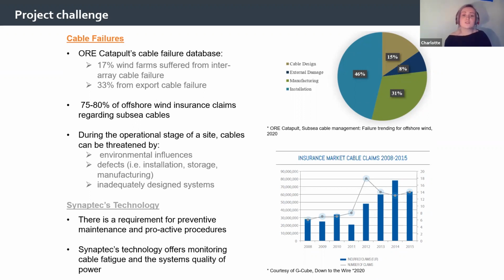There are a multitude of reasons why cables fail, and there are various condition monitoring systems out there to detect various aspects like heat, partial discharge, acoustics, or strain. Synaptec's technology is looking to use differential protection to monitor the cables, and temperature sensors to monitor heat anomalies in the terminations. The Synaptec system was introduced at the Levenmouth turbine through the project Renewable Energy Array Cable and Termination Instrumentation Using Optical Sensor Networks, aka the REACT project.